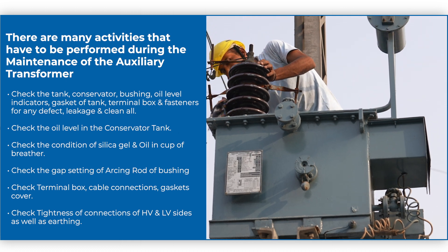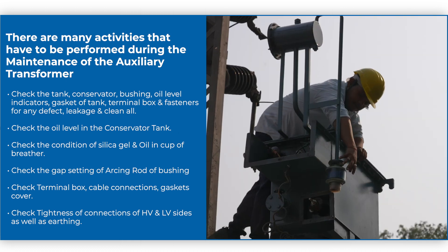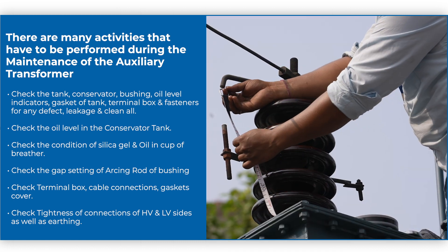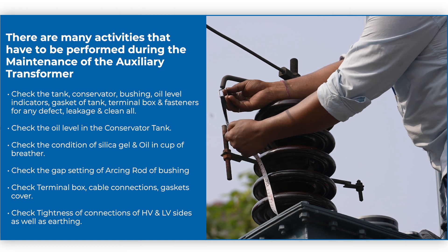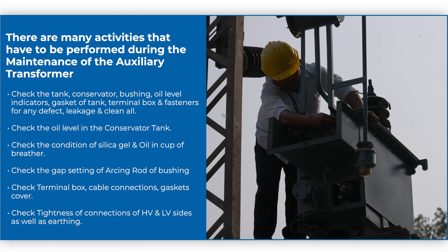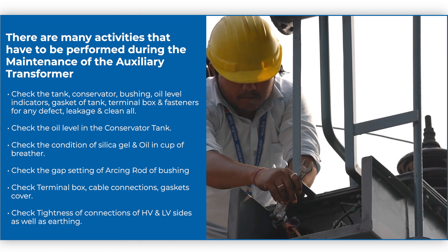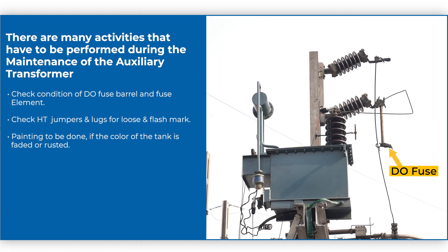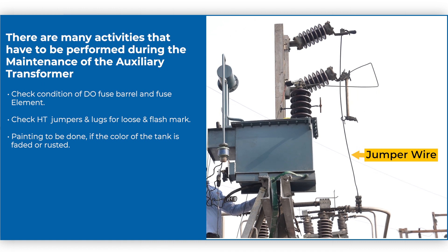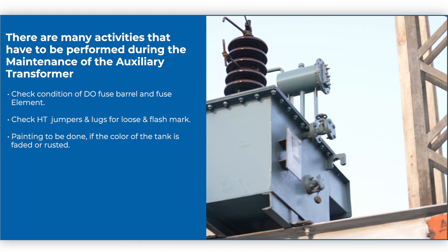Check the oil level in the conservator tank. Check the condition of silica gel and oil in cup of breather. Check the gap setting of arcing rod of bushing. Check terminal box, cable connections, and gasket cover. Check tightness of connections of HV and LV sides as well as earthing. Check condition of DO fuse barrel and fuse element. Check HT jumpers and lugs for loose connections and flash marks. Painting to be done if the color of the tank is faded or rusted.